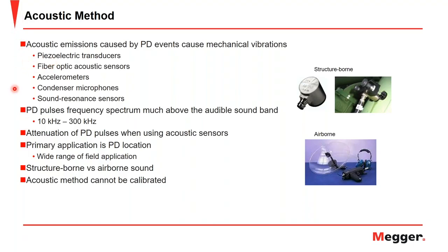And again, this is seen as a complementary measurement where the primary application is partial discharge location. That has a wide range of field applications, such as PD location within GIS, transformers, cables, and other assets. Here we have an example of two different types of sensors, one being structure-borne, which is applied to the structure, whether it be GIS or transformer, and the other being airborne, where you can use this in outdoor facilities and overhead lines to capture PD activity using sensitive microphones.